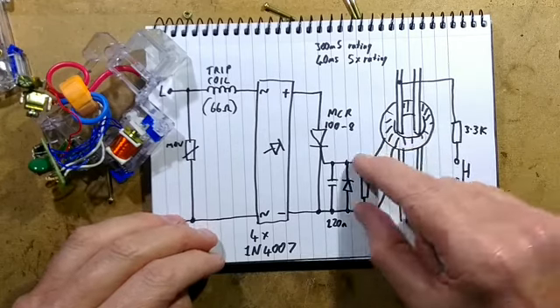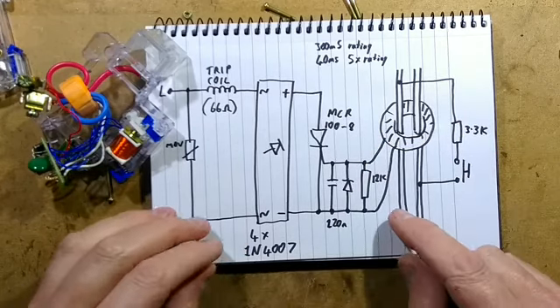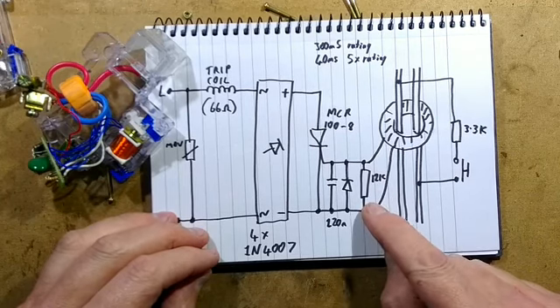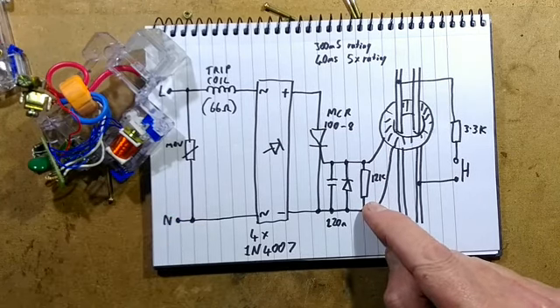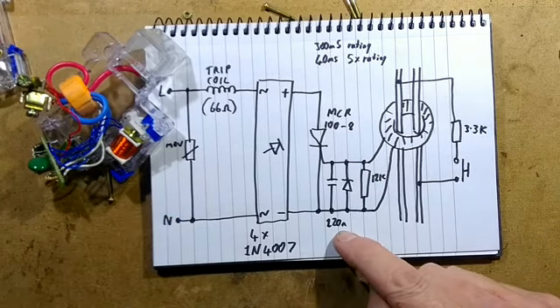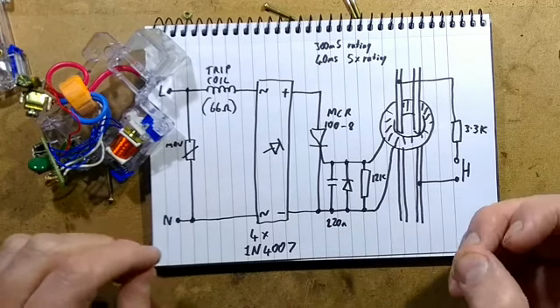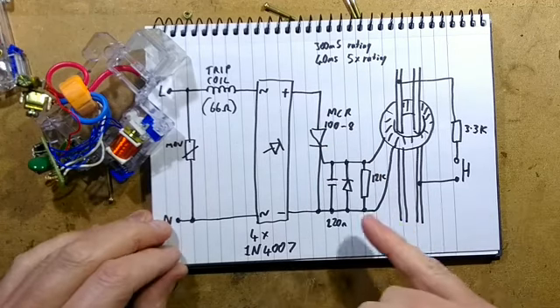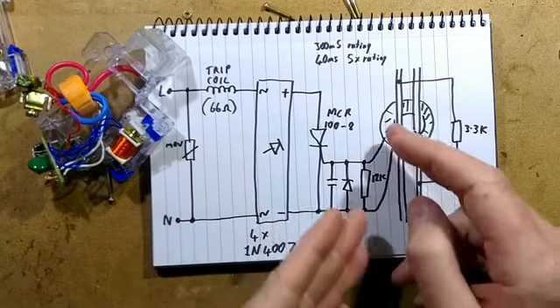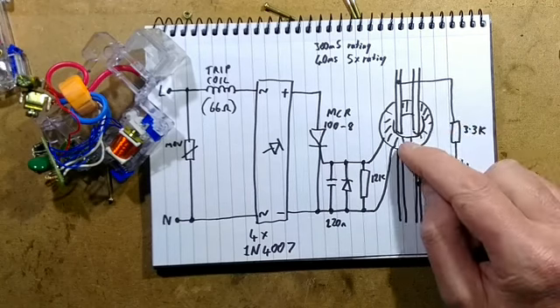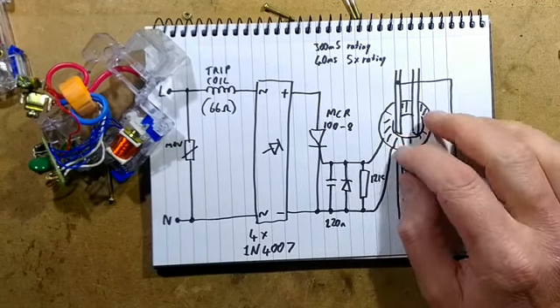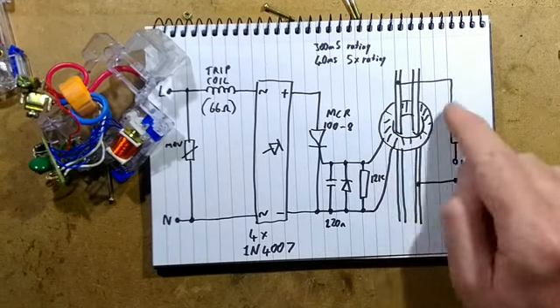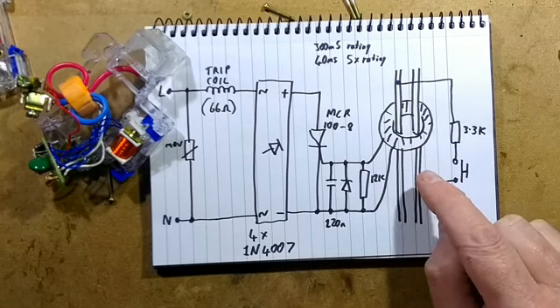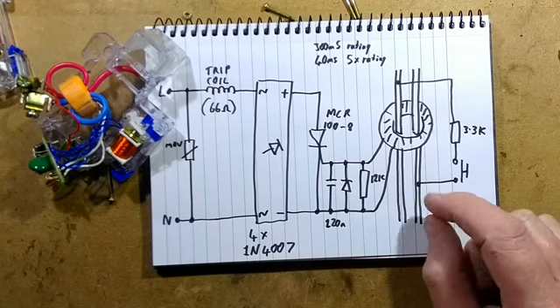And ultimately, the winding that's going to pick up the differential current just has a load resistor of 12K, presumably for some sort of calibration level, a 220 nanofarad capacitor to introduce a very slight time delay and to prevent false triggering of this, and a reverse polarity protection diode, so that in the event of fault current flowing, it's not going to saturate this core. Could that happen? This core is not suitable for DC faults. Not many RCDs or GFCIs are.